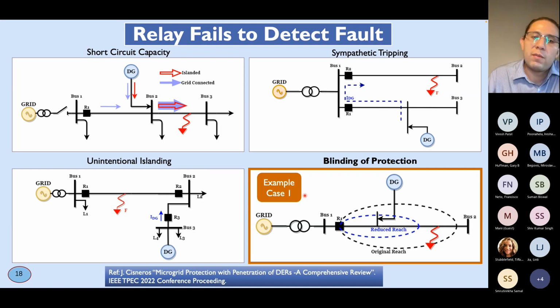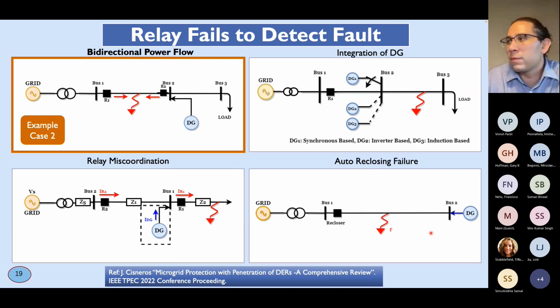Traditional way, we can detect it, but because of the reduced reach due to the microgrid integration, to the distribution generation integration within the grid, the relay might not be able to see the fault itself, because the current is interacting with the grid or the substation and as well with the distribution generation. So in this case, it's possible that the relay won't trip, and this is actually a very big problem that is happening nowadays. Among the other case studies that I mentioned, we have the bidirectional power flow, the integration of DG, relay miscoordination, and auto reclosing.